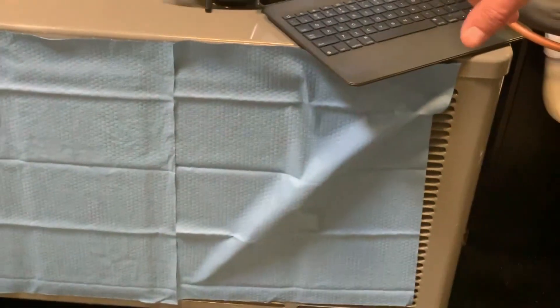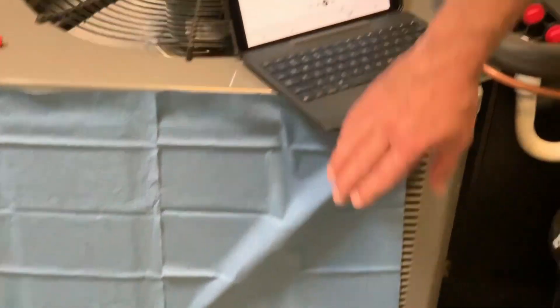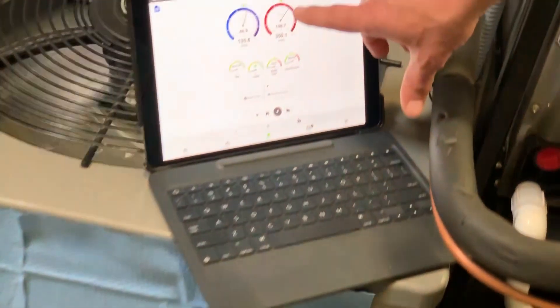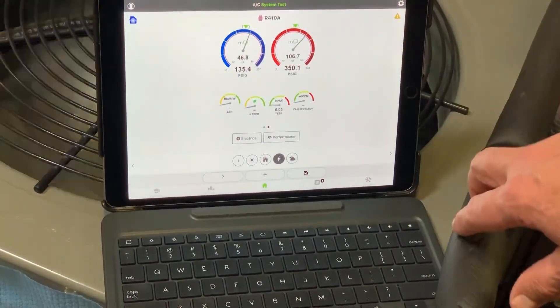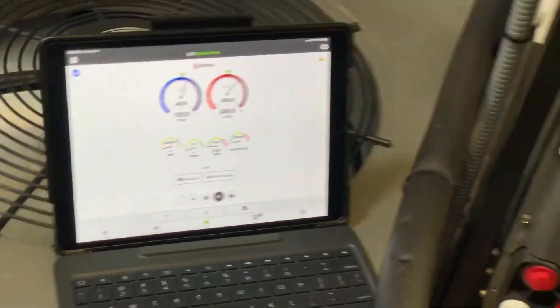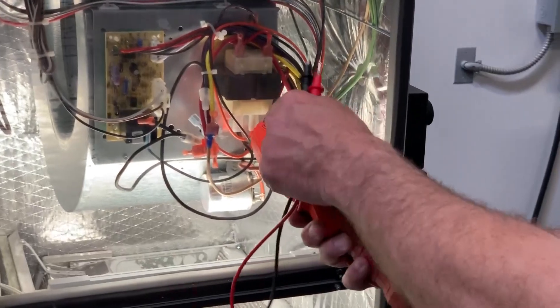If you look down here at this condensing unit, I've got it sort of blocked off at the condenser fan so I can block off part of the coil. You can see I'm running high head pressure, and this would be very typical of what you might see with a dirty condenser coil. So maybe I want to show the customer a before and after — I'm going to clamp the meter onto my blower motor lead.